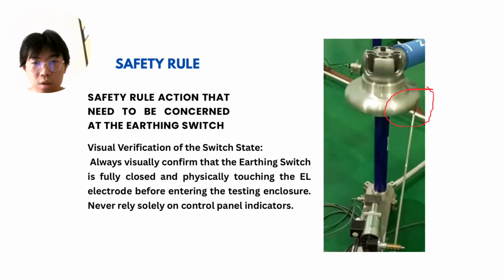The next is visual verification of the switch state. Always visually confirm that the Earthing Switch is fully closed and physically touching the electrode before entering the testing enclosure. Never rely solely on control panel indicators.